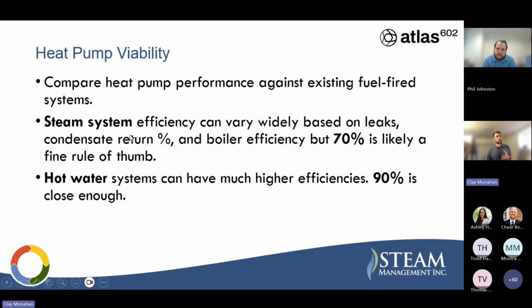Okay, so just switching back here to the heat pump viability, just establishing some base cases here. So hot water systems, these can have much higher efficiencies than a steam system. 90% is close enough, but even some of these direct contact units can have really high efficiencies. You're still going to have losses through insulation and all that as you distribute the hot water, but these systems are going to have higher efficiency than their steam counterparts. But typically, for most of the folks on this call, the relevant base case is going to be that steam system.